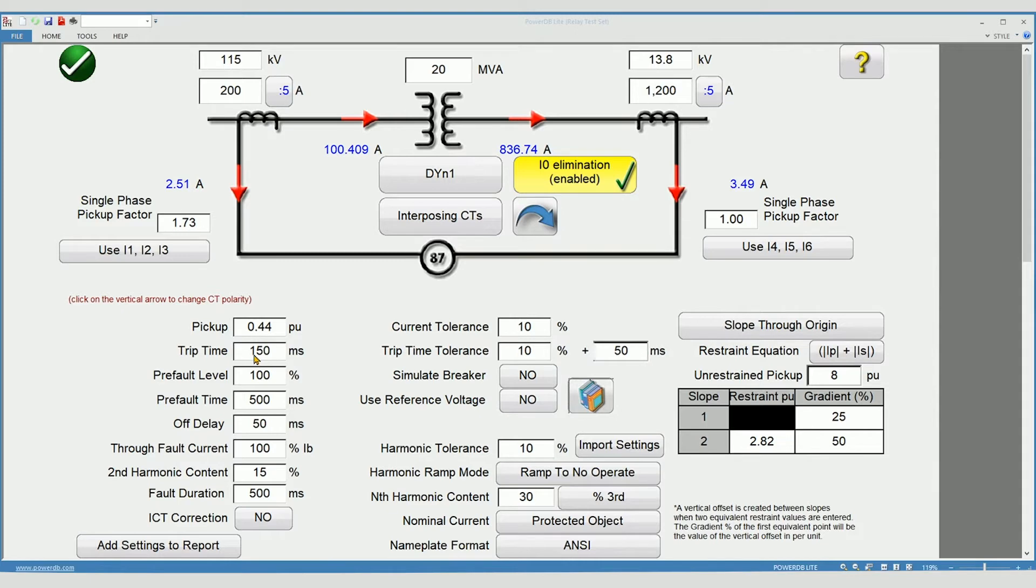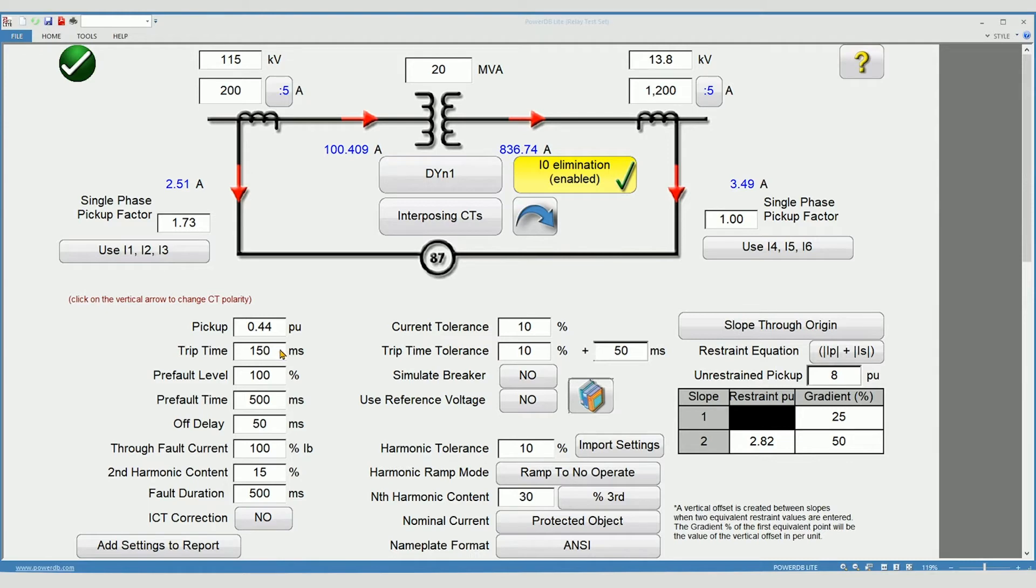Trip time is the expected trip delay for the relay to close its contacts. Keep in mind that no relay is instantaneous. There is always a propagation time for the relay to close its output contacts. Trip time tolerance is the allowable error for the trip time.